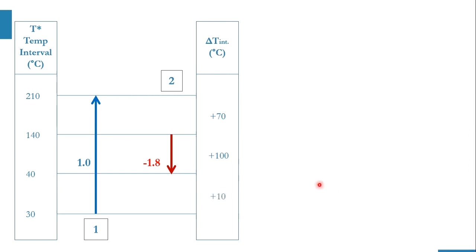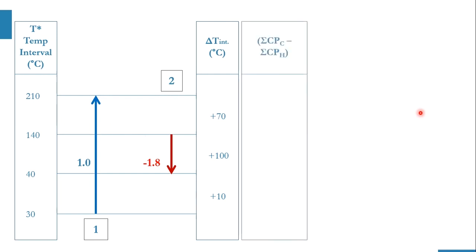After gaining experience you can start directly here. We need to calculate CP of C minus CP of H, then multiply by delta T interval to get delta H. In the first interval there is only stream one (cold stream, CP = 1), so no CP of H — the sum is just plus 1. In the second region (delta T = 100°C), both streams are present, so CP of C minus CP of H gives 1 minus 1.8 = minus 0.8.